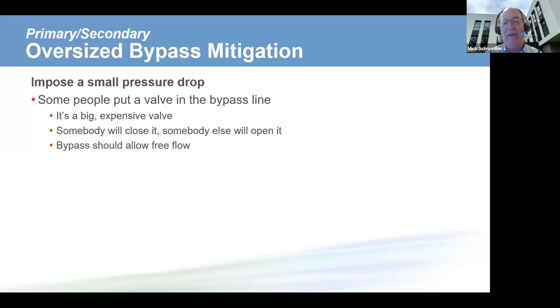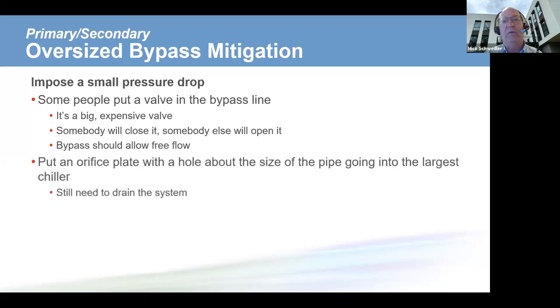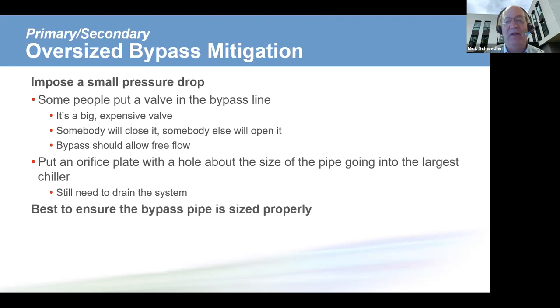So valves in bypass line can get you in trouble from an operational standpoint. Another way to do it, to impose a pressure drop, would be to put a small plate with a small hole in it, an orifice, if you will, to impose some pressure drop. But in either case, you have to drain the system to install those. So once this is installed out in the field, it frankly is hard to fix. So the best part is to basically make sure the bypass line is sized properly.